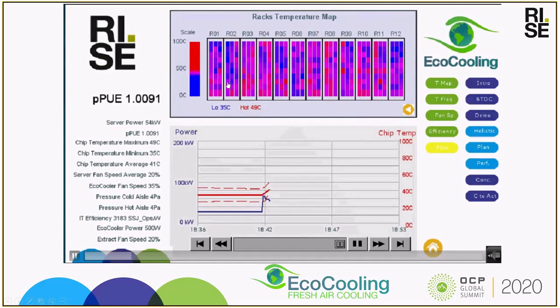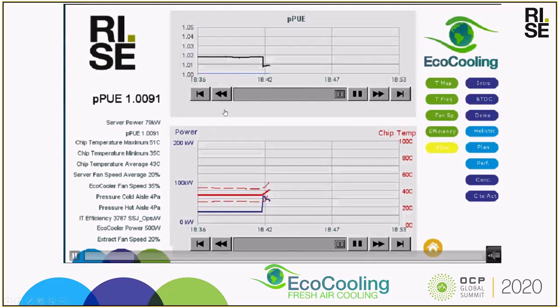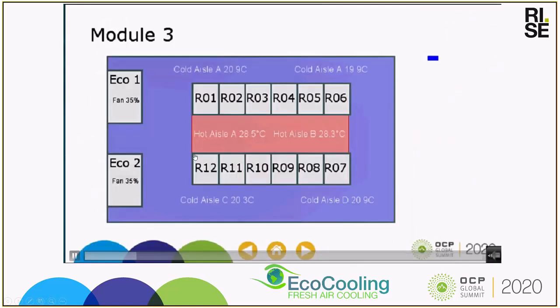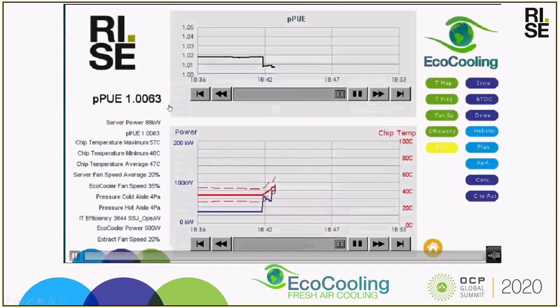So the temperature map you see here is based on the range of temperatures from the coolest to the hottest CPU. This is the arrangement of the racks. Rack 1 and Rack 12 are closest to the EcoCooling units, and we're monitoring the aisle temperatures of the hot and the cold aisle and the fan speeds of the EcoCooling units.